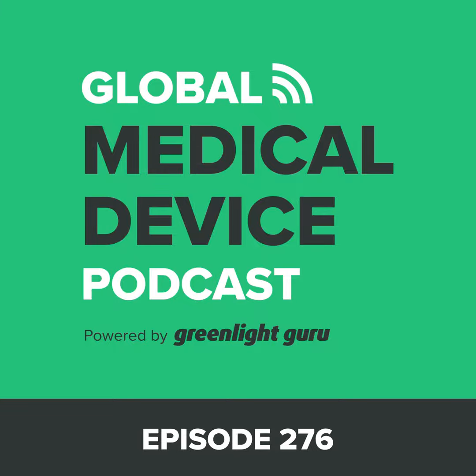So one of the things that you might highly recommend is that you make sure you engage with a notified body that, first of all, has made commitments to review products under the MDR and IVDR as appropriate, and get on their list and start to collect your data according to the MDR so that when your schedule comes up in their timing, you're ready to go, because there's some deadlines. Legacy products with old certificates, and again, sometimes they expire over the course of time, but if you're able to use them without a design change, and the certificate's still valid, there's a deadline for those.